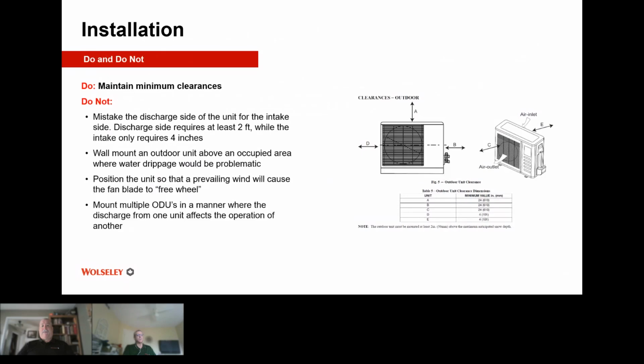All right, the do's and don'ts of installations. Okay, let's look at the do's. Let's maintain minimum clearances. So for the outdoor unit, depending upon your brand, you want to try and maintain that you have enough airflow that comes from the air inlet as marked by E. We want to make sure that we have adequate air coming in the back to go over our coil, to be pulled through by our fan so that we can have the proper exchange.